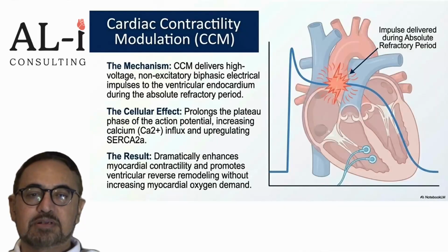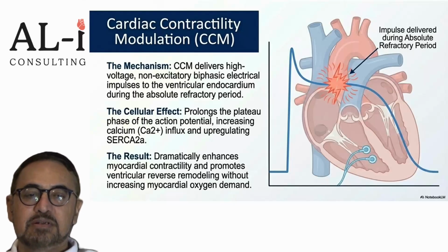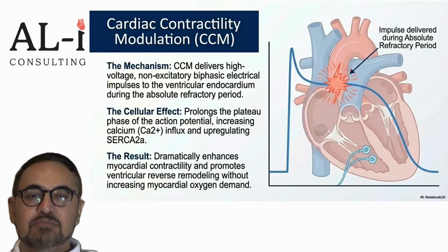CCM, cardiac contractility modulation, is very different. CCM delivers high voltage, non-excitatory biphasic impulses during the absolute refractory period. Because it is delivered when the myocardium cannot be depolarized again, it does not create a new beat and does not function as a pacemaker.